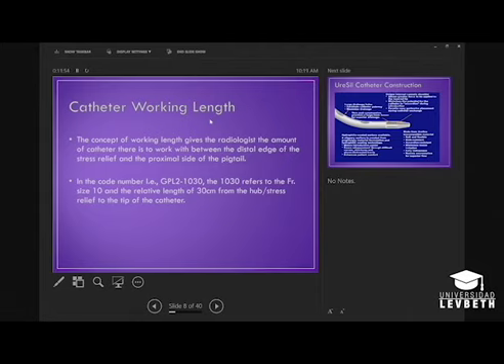On all of our catheters, the packaging shows the working length, and the product code tells the total length. So for example, in this code, GPL2-1030, 10 references the French size, and 30 references the length from the hub to the catheter tip. 10 French, 30 centimeters. That is the total length. The working length will be inside the catalog that you get, a full catalog. It'll tell you the product code, which will tell you the total length, and then it'll have the size and length in the middle that tells you the working length. So in this specific catheter, the total length is 30 centimeters, and the working length is 21 centimeters.